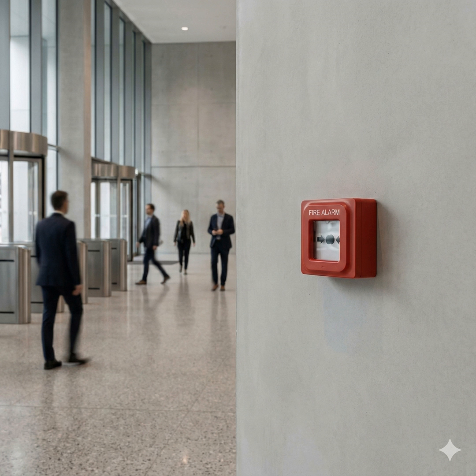It would, and that's where rate of rise detection comes in. These sensors trigger not on an absolute temperature, but on the speed of the temperature increase, typically if it jumps more than 12 to 15 degrees Fahrenheit per minute. So it's looking for a sudden, aggressive fire. Yes, but there is a critical limitation here: thermal lag. The sensor's element takes time to heat up and match the ambient temperature. In a very dusty environment, or if the heat source is far away, this lag can affect performance.